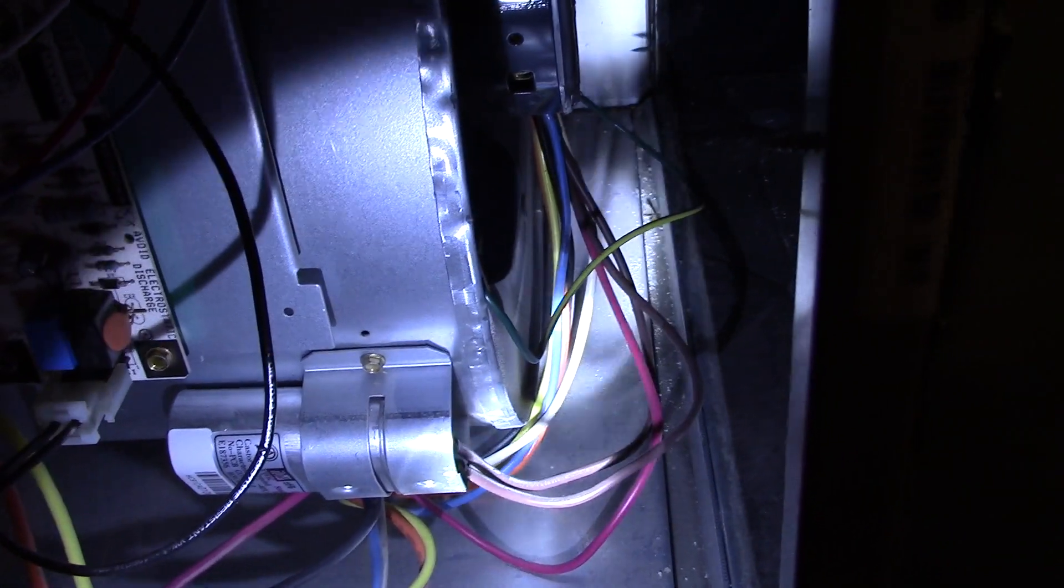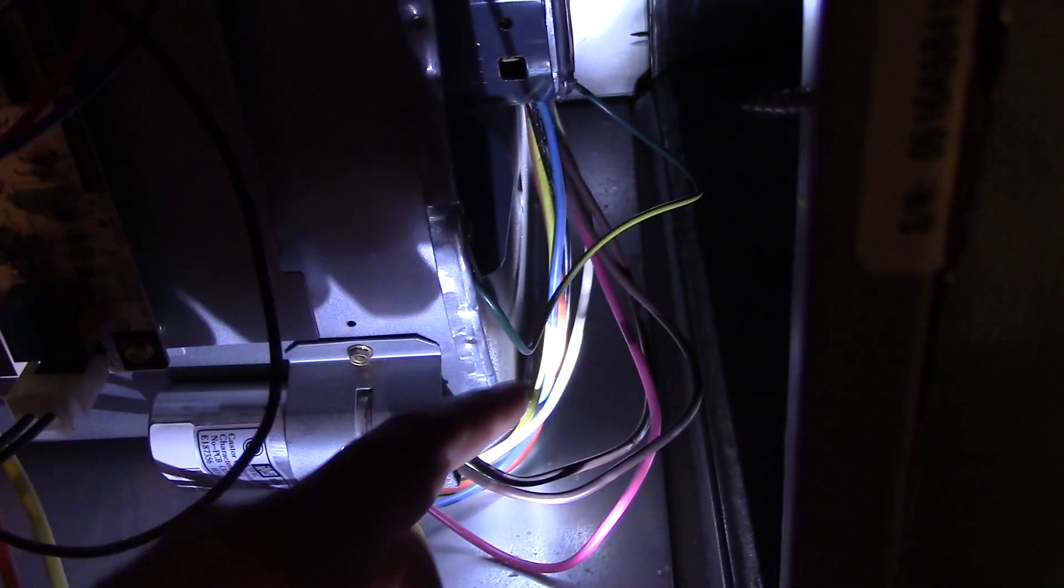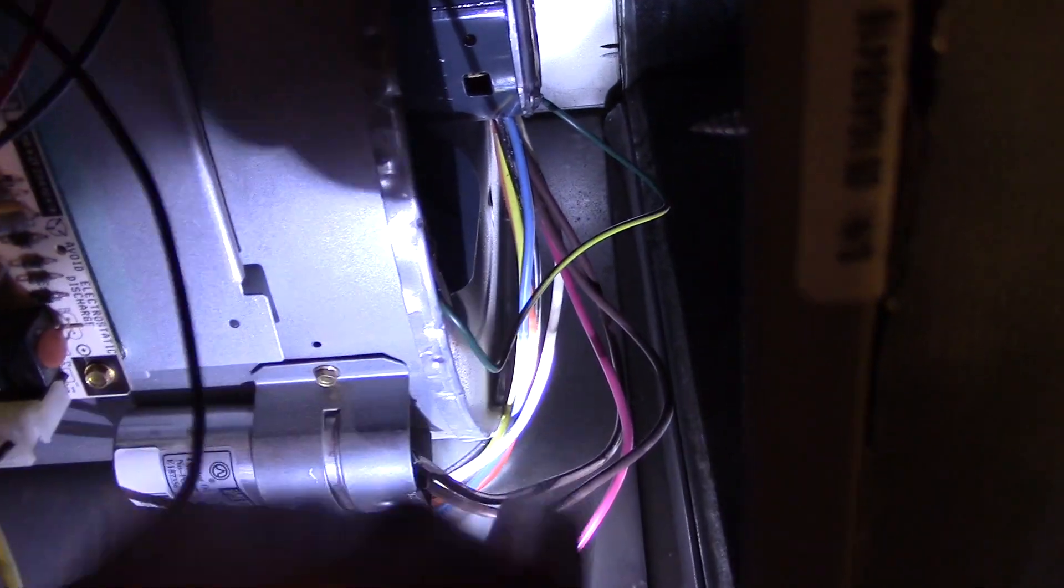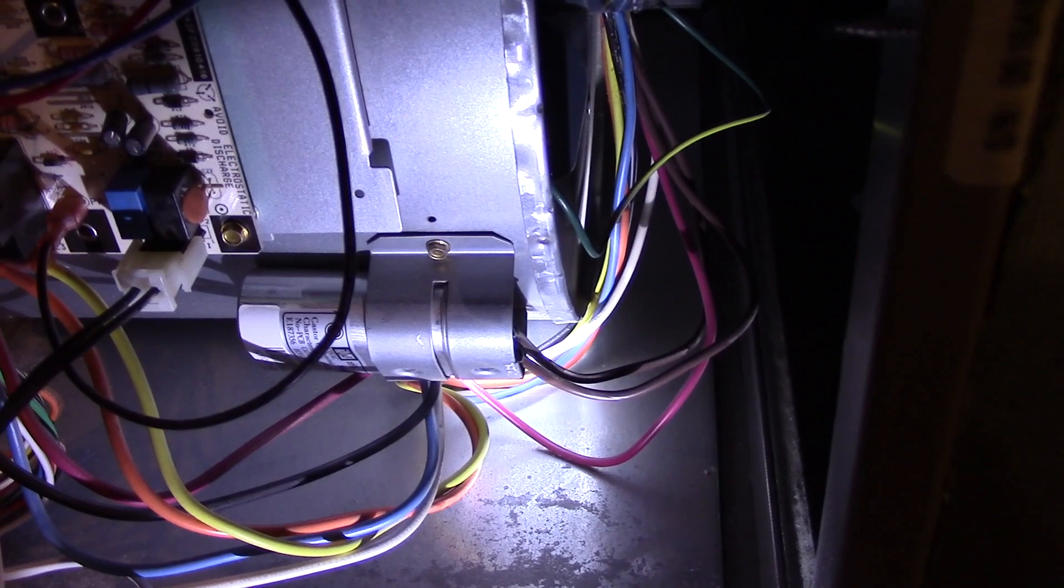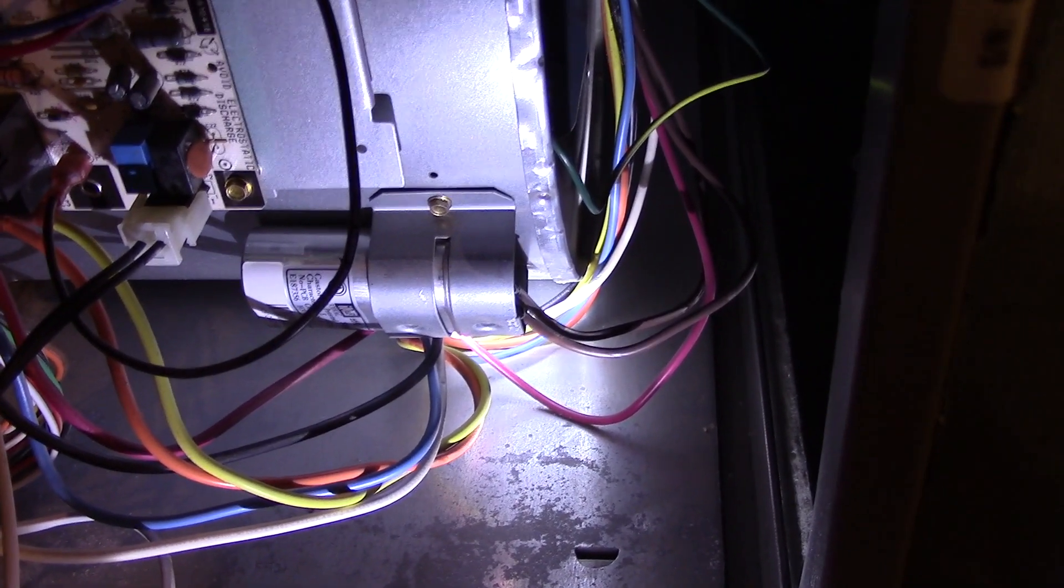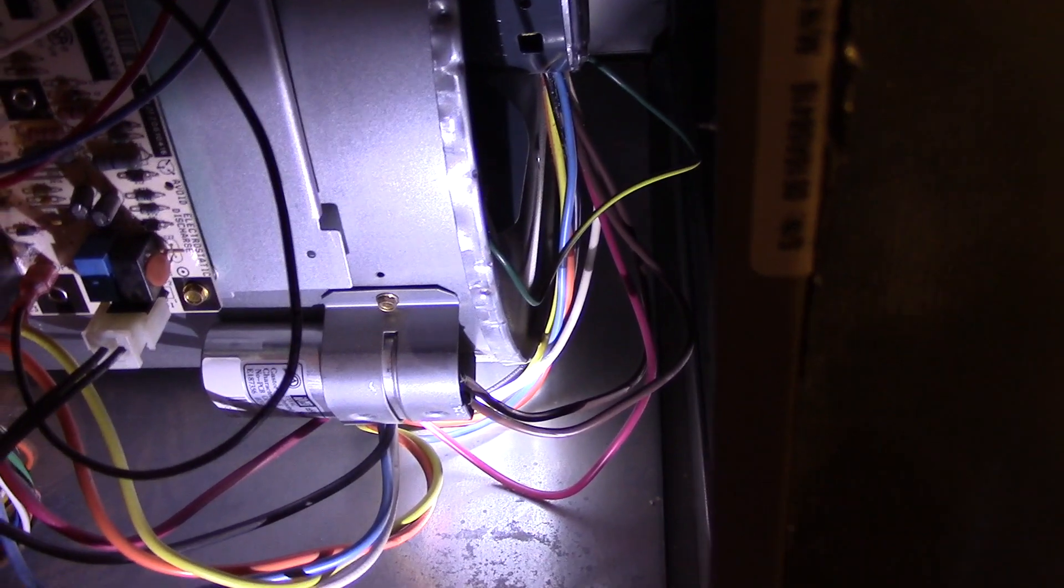Now there's also a white wire there. That's your common wire or also called your neutral wire. Don't mess with that wire. Leave it exactly where it's connected because that doesn't pertain to the speed. What does pertain to the speed is if you look inside here, there's a black wire, a yellow wire, an orange wire, a blue wire, and a red wire. In most furnaces, the black wire is high speed and the red wire is low speed.